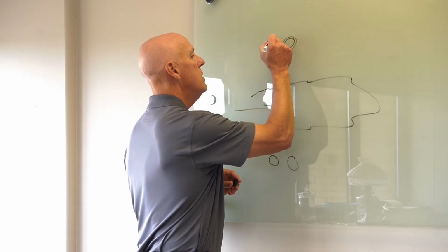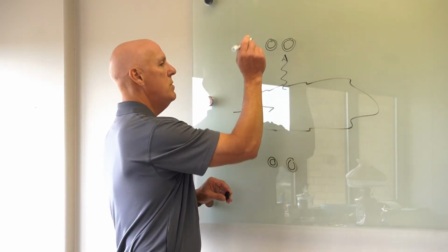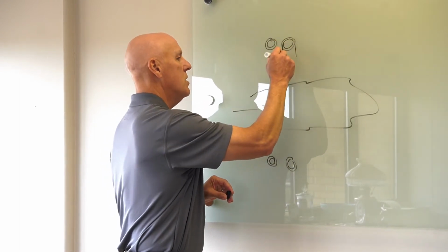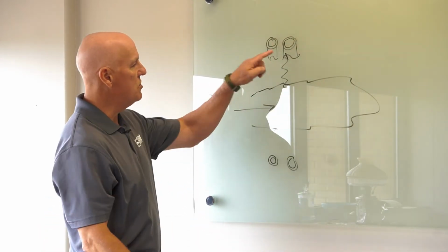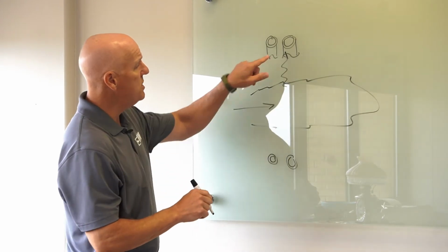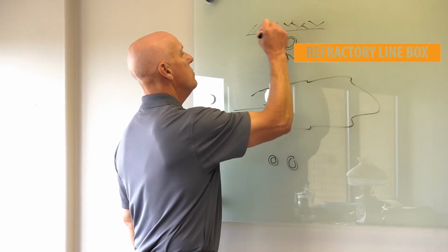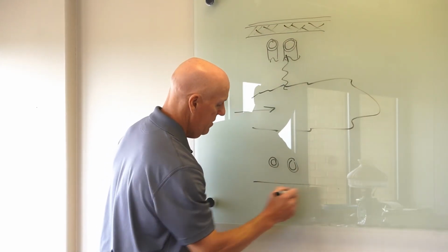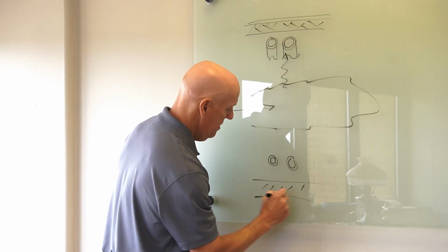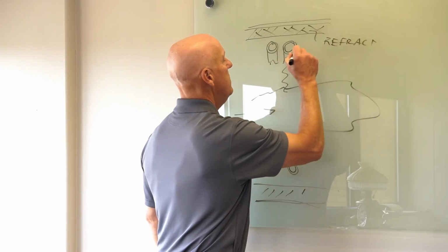Obviously in this tube, I'm going to draw these little circles here to show that we've cut it away. In these tubes, there's fluid that's flowing around, and I'm just going to kind of draw it like that, right? Because it's a giant hoop around this flame. So there's fluid in there, and I'm transmitting heat to that. And then behind this is a refractory lined box, or radiant box, okay? This is refractory, and then there's steel plate on the outside of that. These are tubes.